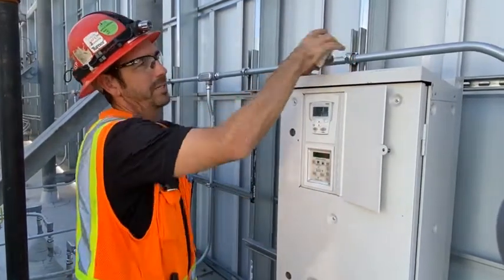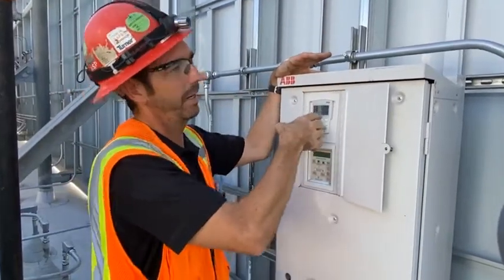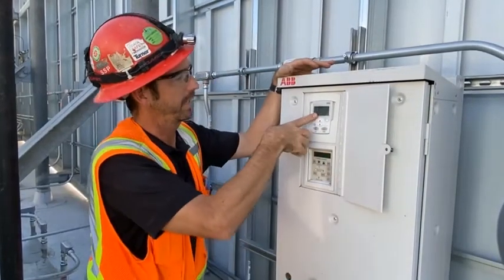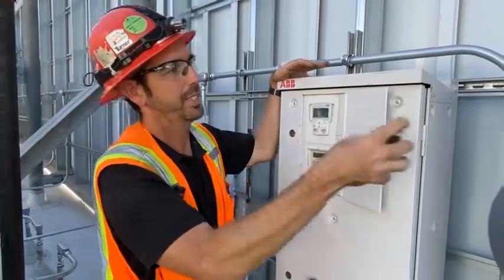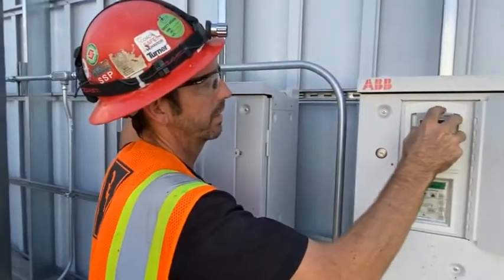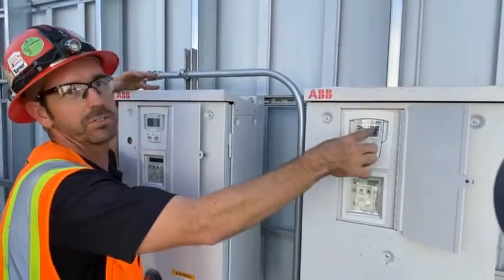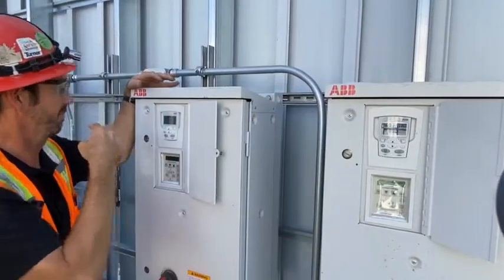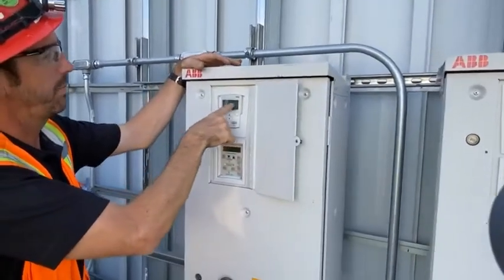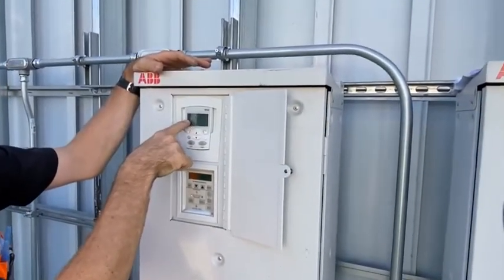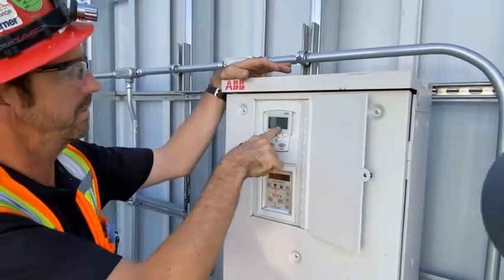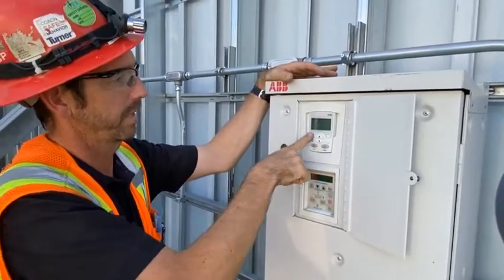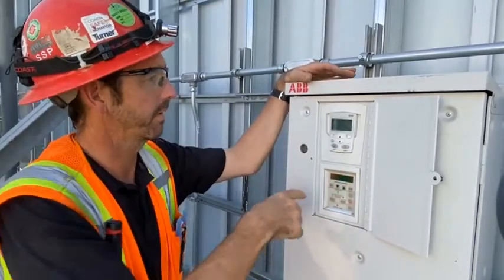The keypads are interchangeable. Since I have it in here, I have the program saved in here. I can change these keypads because the drive itself is already storing the data in it, right? Anytime you take off the keypad, if it's not in auto, you'll get a fault 10, which is a panel loss. We lost communication to the panel. We can just reset that. We know we took the keypad off, okay?